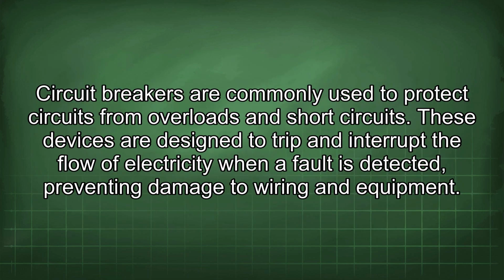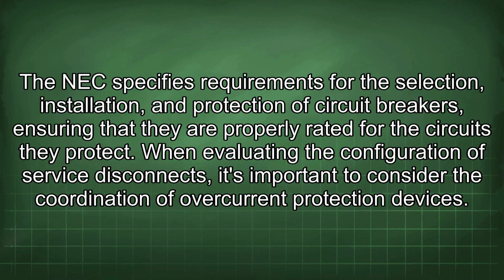Another relevant factor is the type of overcurrent protection used in the electrical panels. Circuit breakers are commonly used to protect circuits from overloads and short circuits. These devices are designed to trip and interrupt the flow of electricity when a fault is detected, preventing damage to wiring and equipment. The NEC specifies requirements for the selection, installation, and protection of circuit breakers, ensuring that they are properly rated for the circuits they protect.